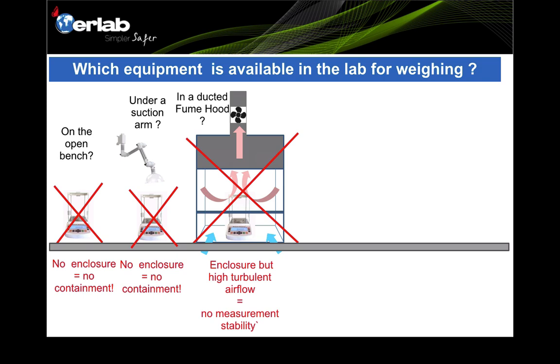The third situation is using a ducted fume hood. No doubt there is enclosure and protection, but the problem is fluctuations — because a ducted fume hood generates high turbulence airflow inside the hood, making it near impossible to get very accurate measurements for a high accuracy balance. For instance, with an analytical balance, 4 to 6 decimal place measurements are near impossible to perform inside ducted fume hoods.